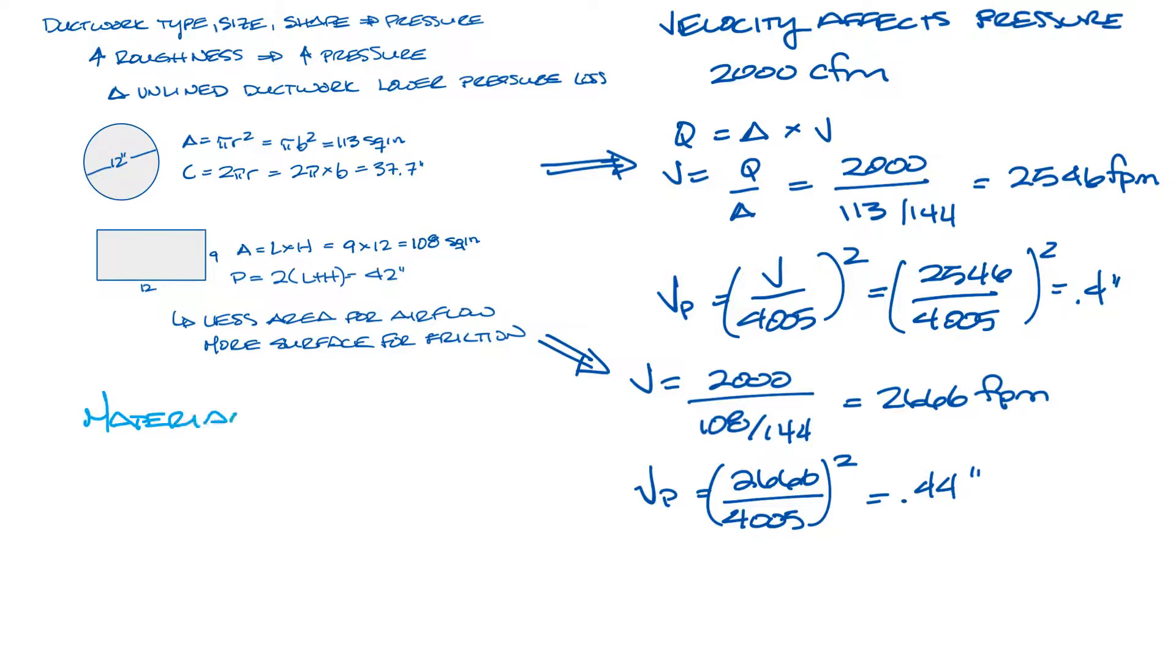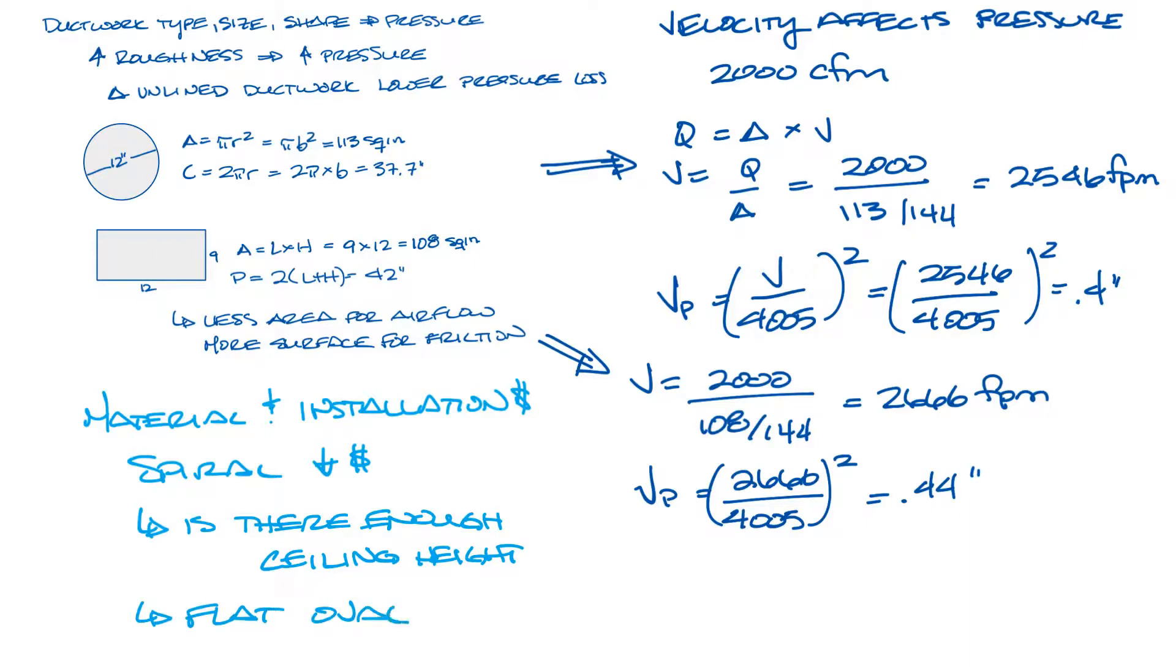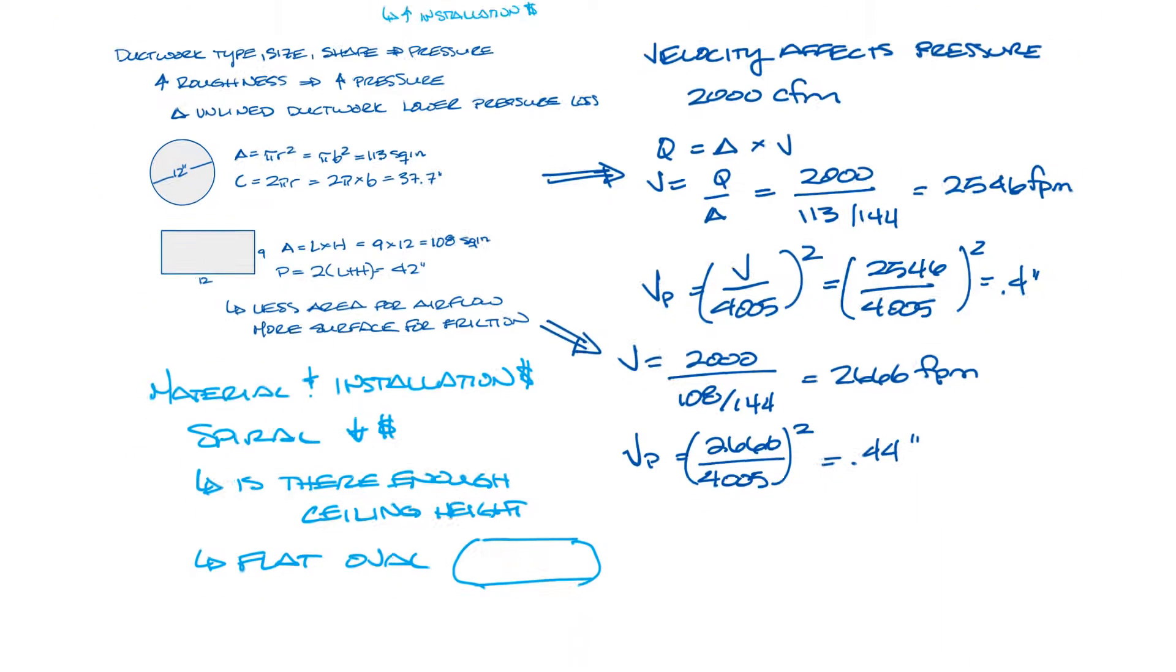You also have to consider the material and installation cost. Spiral duct may be less expensive and requires less ceiling, so it may be a better option all around in this example. But what if you were comparing 24 inch spiral to a rectangular duct? In this case, you may not have enough ceiling height to install the 24 inch spiral, so you would have to make a decision about using a less tall rectangular ductwork or a flat oval, and that might be your best option.